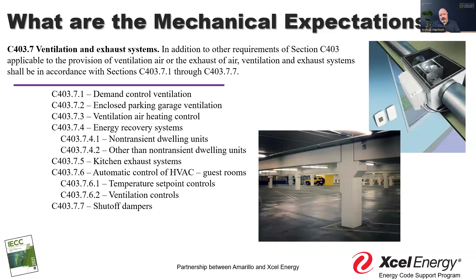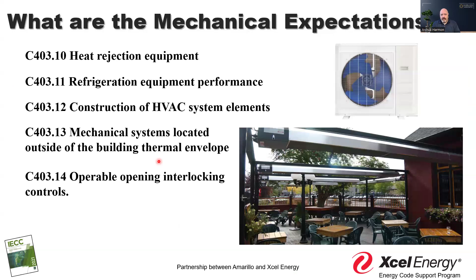That's one of the expectations of the code - that we think about design, distribution, and construction. The construction of the HVAC system matters in both commercial and residential applications. The mechanical code tells us we need to insulate, but the energy code gives more flexibility: if you install the ductwork inside the building's thermal envelope, you don't have to insulate as much, because we're mainly trying to protect against condensation rather than worrying about retempering the air mid-flow.